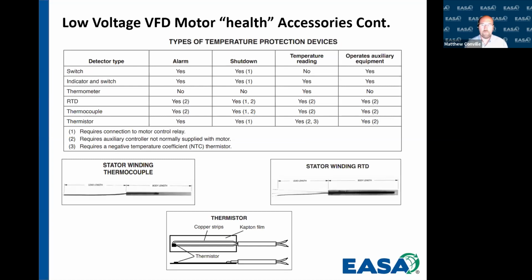Now, not all temperature detectors are actually created equal. A lot of times we're going to see electric machines outfitted with switches, or colloquially a click-on or a thermostat. And these are great for setting an alarm or setting a shutdown or to operate auxiliary equipment, but what they can't do is actually give you a temperature reading. Now, you could use a thermometer, and the thermometer might actually give you a temperature reading, but it's not going to give you any alarm or trip set points. So the things that we're going to want to look at using are going to be RTDs, thermocouples, and thermistors. If we're going to use a thermistor, we need to make sure that it's a negative temperature coefficient thermistor for temperature reading.